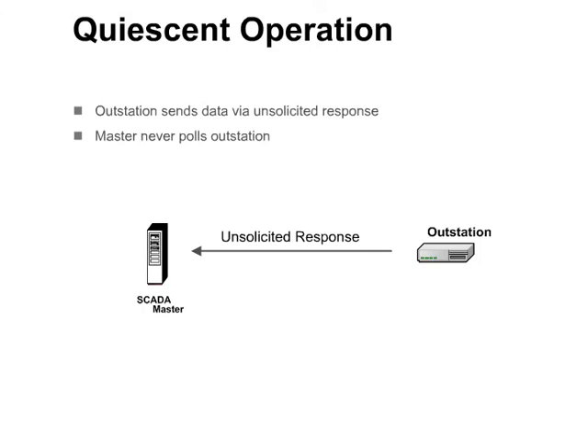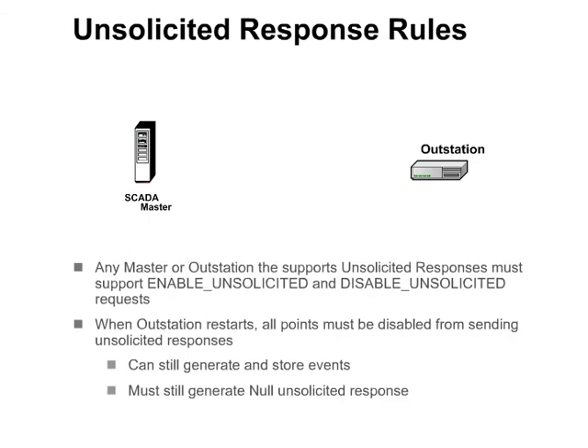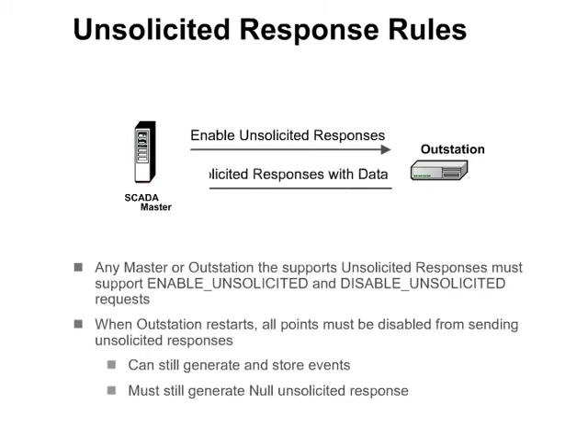The DNP-3 specification requires that any master or outstation device that supports unsolicited responses must also support the enable and disable unsolicited response requests. Furthermore, the specification states that when an outstation restarts, all points must be disabled from sending unsolicited responses. The outstation must still send its initial null unsolicited response — that is, an unsolicited response with no data. However, it may not send unsolicited responses with data until it receives an enable unsolicited response request from the master. Note that the outstation may still be generating and storing events before it receives the enable unsolicited response request; it is just not allowed to send those events via unsolicited responses.